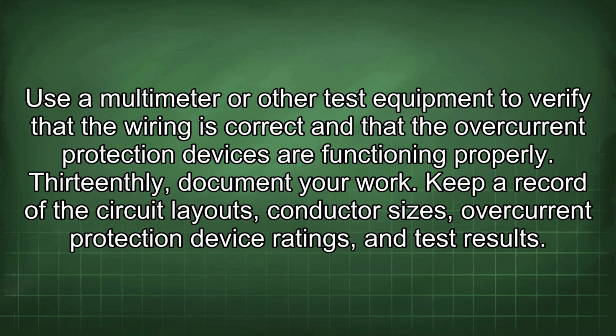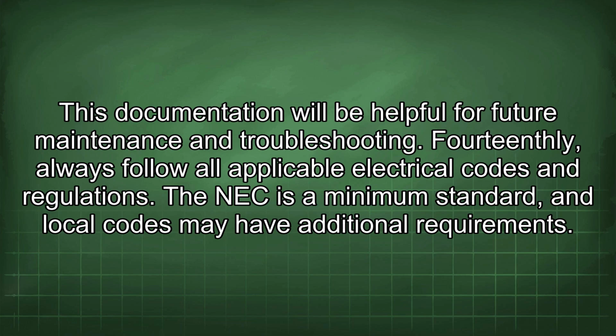Use a multimeter or other test equipment to verify that the wiring is correct and that the overcurrent protection devices are functioning properly. 13th, document your work. Keep a record of the circuit layouts, conductor sizes, overcurrent protection device ratings, and test results. This documentation will be helpful for future maintenance and troubleshooting.